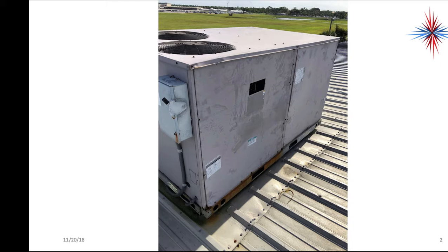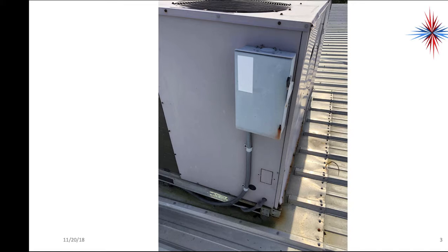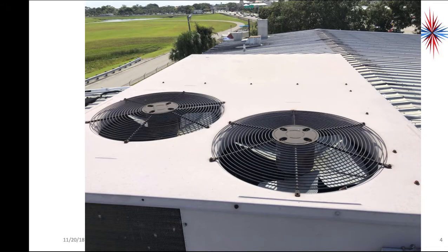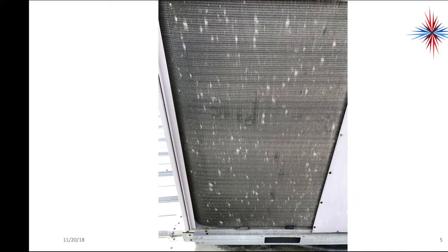The first thing we do is basically make notes of any damage on the outside of the unit. Okay, so we're missing a condenser panel here. The disconnect is showing some signs of rust. There's screws laying on top of the disconnect. The top of it's not in bad shape. There's no major dents or bruises. The fans are not operational, and there's rust on the sides of the motors, which just shows age. It's not anything new and unusual.